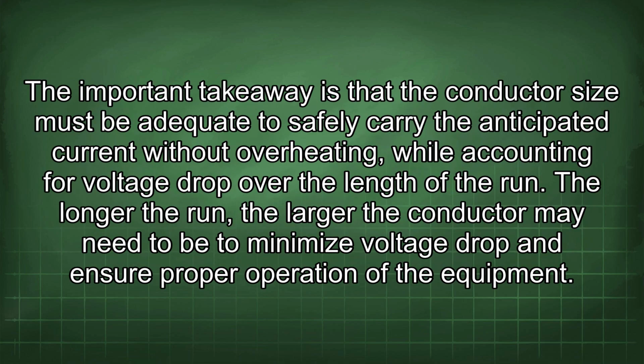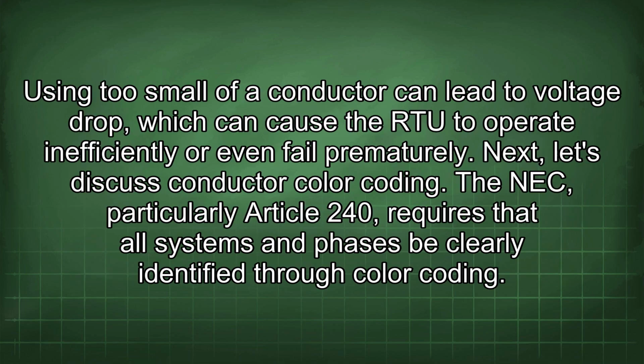The important takeaway is that the conductor size must be adequate to safely carry the anticipated current without overheating, while accounting for voltage drop over the length of the run. The longer the run, the larger the conductor may need to be to minimize voltage drop and ensure proper operation of the equipment. Using too small of a conductor can lead to voltage drop, which can cause the RTU to operate inefficiently or even fail prematurely.